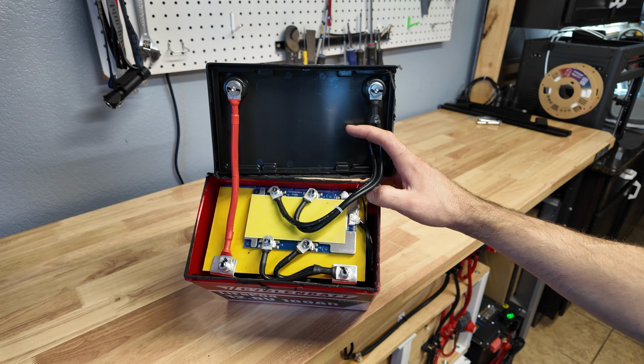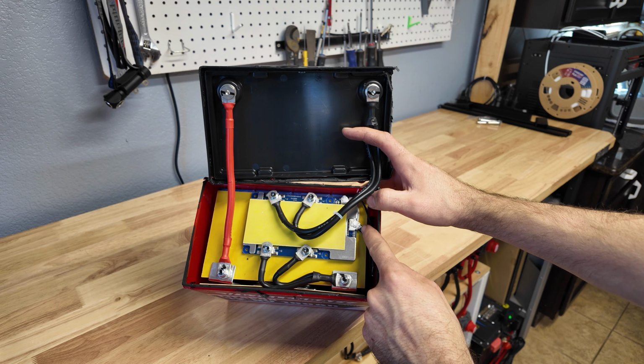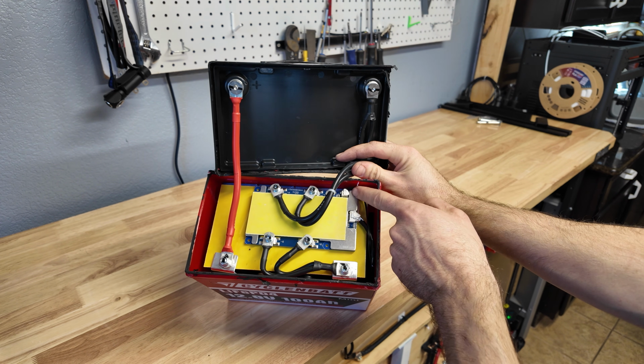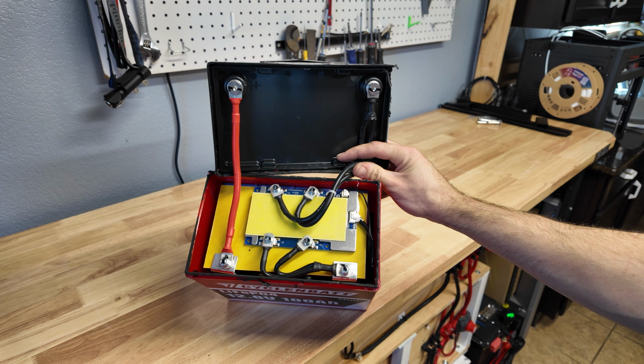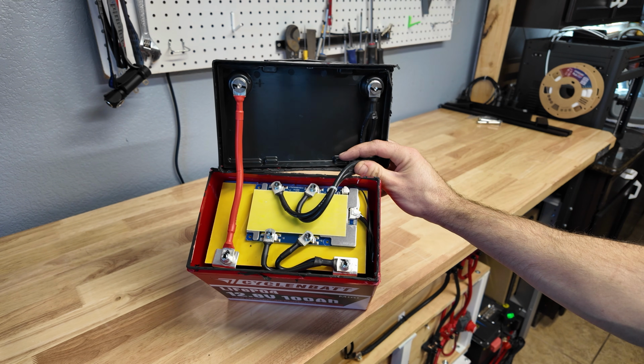Bolted terminals, no soldering there. Our balance harness is secured right here. They even put a little bit of goop on the connector. There's our temp sensor, so we're gonna pull the temp sensor out of the battery in order to test the low temp cutoff. Connections at the top look good.